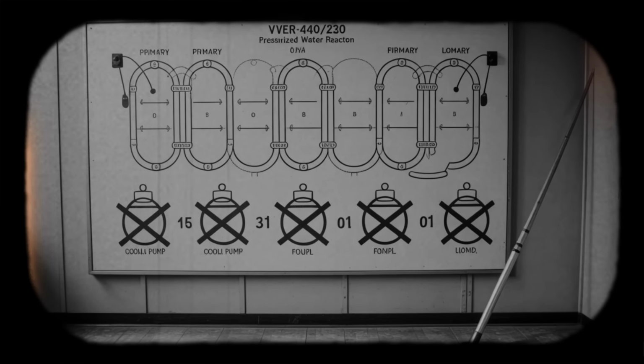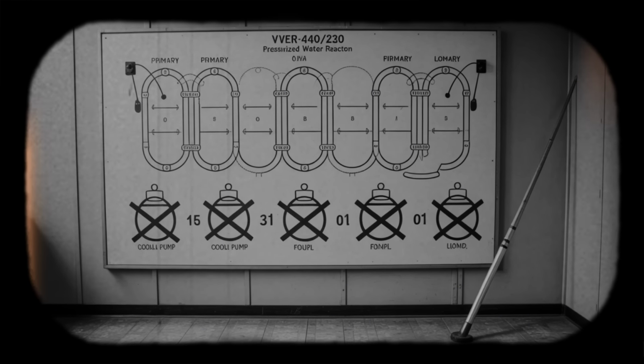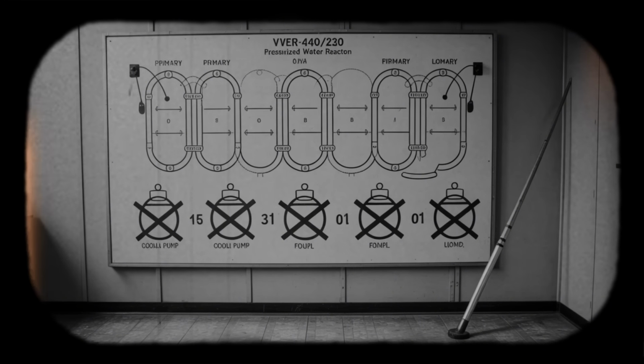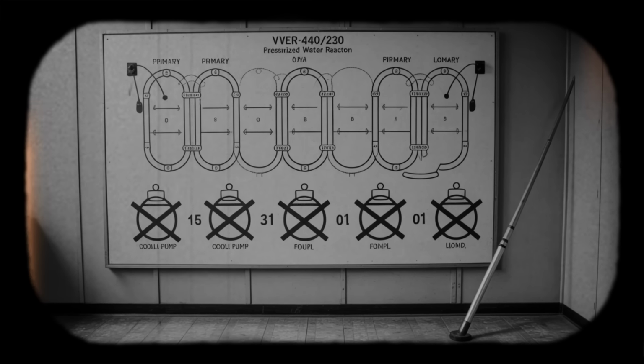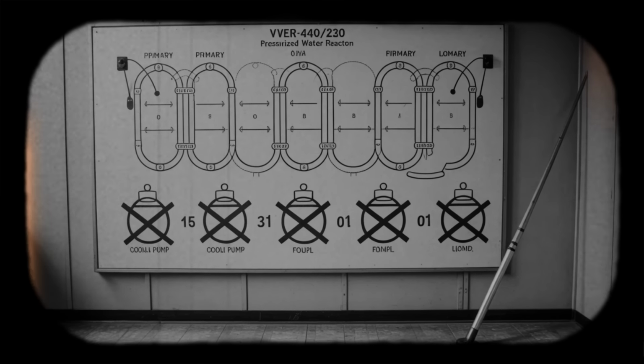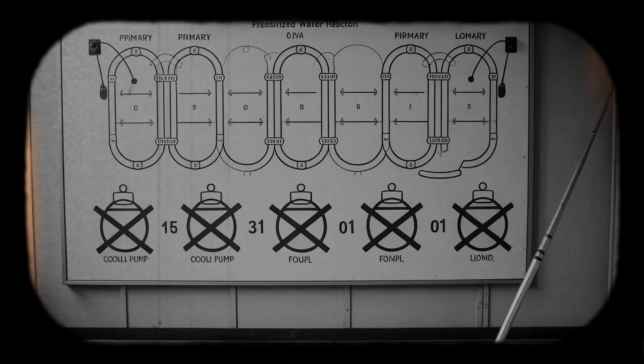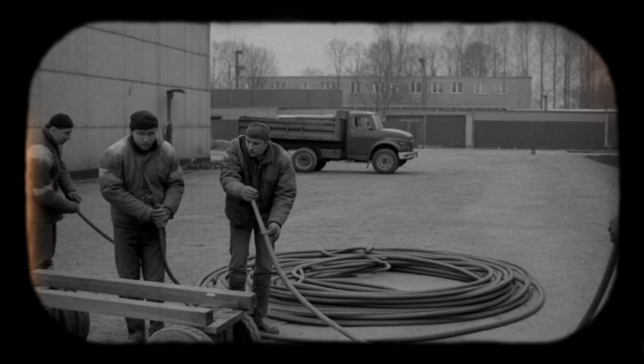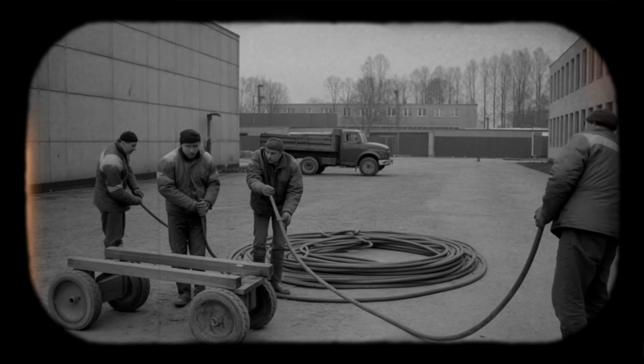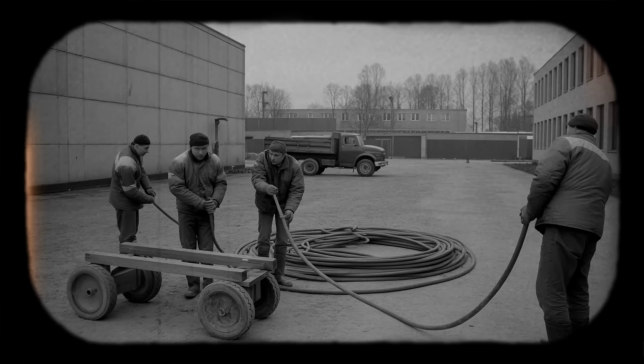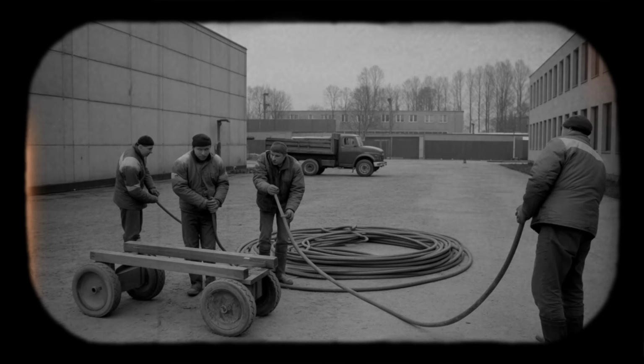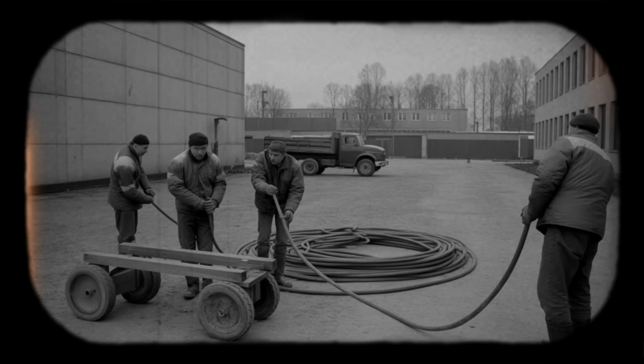International assistance programs, EU PHARE, TACIS, bilateral agreements, prioritized safety upgrades for Soviet-designed reactors in Central and Eastern Europe. Greifswald's experience informed backfitting requirements: improved fire barriers and detection in cable ducts, rerouting of cables to enhance train separation, additional or reconfigured emergency feedwater systems, and upgraded emergency power with better physical protection and control cable segregation. For some plants, these upgrades proved economically feasible. For others, including all VVER 440 V230 units, the scale of required modifications was deemed cost-prohibitive given the plant's age and remaining operational life.